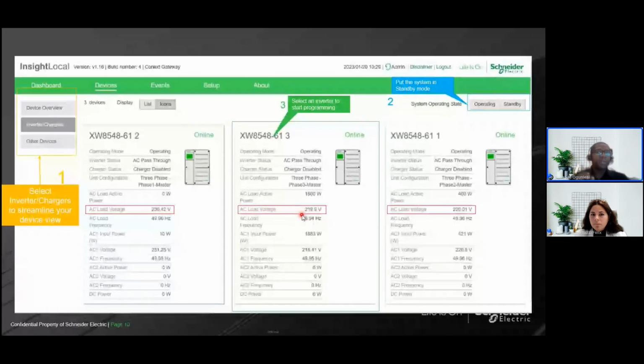If we didn't calibrate those output voltages, instead of inverter one and inverter two collaborating to supply the load, inverter one is going to try and backfeed power to inverter two because the voltages are way off, and inverter one is in fact seeing inverter two as a load. So you'd have to do that sort of calibration, which is a very important step for you to see here.